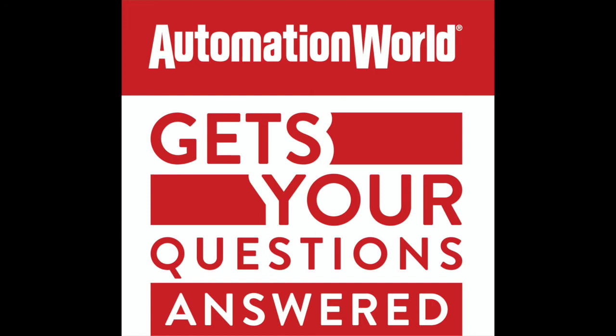On the operations side, again, lower MTBF numbers mean that production assets are failing more frequently and hurting overall productivity, right? So there are some situations where operators could probably directly influence that MTBF time as well. If you have an operator that knows how to tweak machine parameters to increase throughput, but it also decreases the MTBF and makes the line go down more often, maybe your overall productivity goes down, right? So it's one of those numbers that can help you to understand and balance the overall effectiveness of a line and your influences on overall throughput.